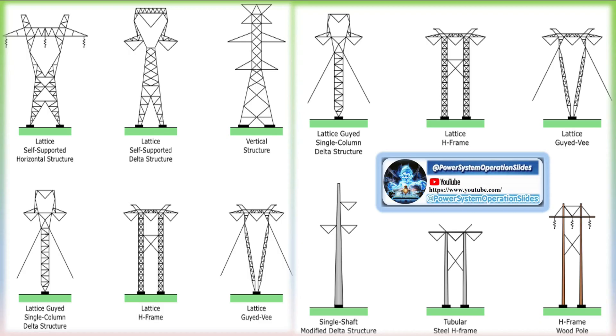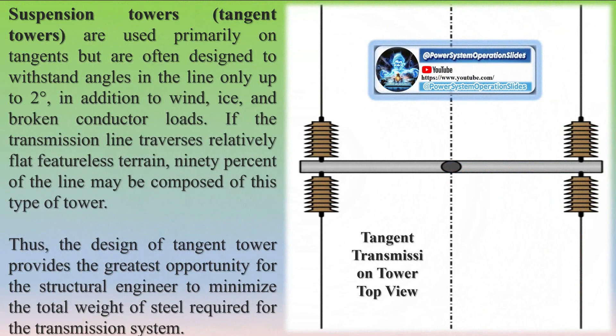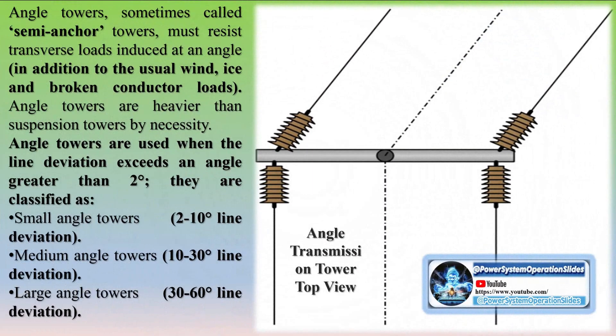The structures commonly used on transmission lines are either lattice type or pole type. Lattice structures are usually composed of steel angle sections. Poles can be wood, steel, or concrete, and each structure type may be self-supporting or guy-supported by cables. Pole type structures are generally used for voltages of 345 kV or less, while lattice steel structures are favored for higher voltage levels. Wood pole structures can be economically used for relatively short transmission distances and lower voltages.